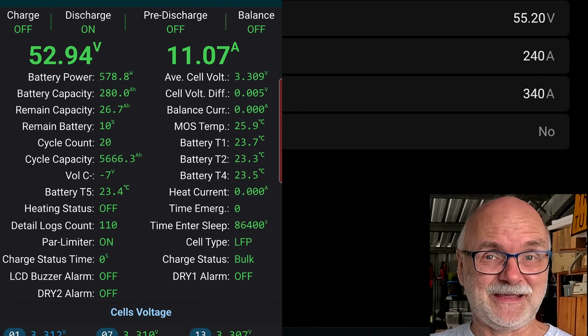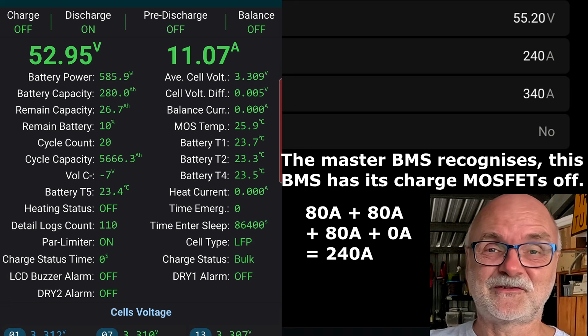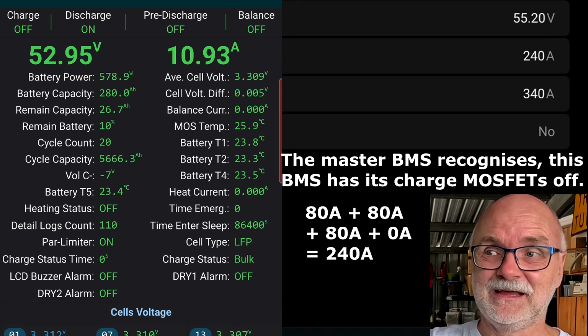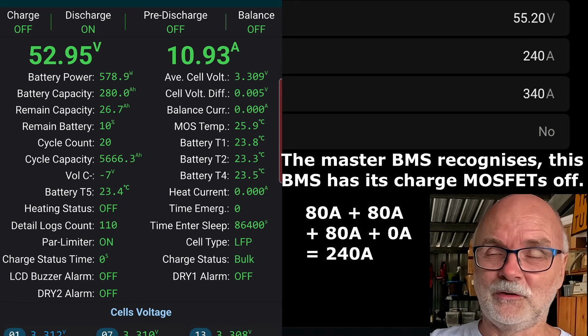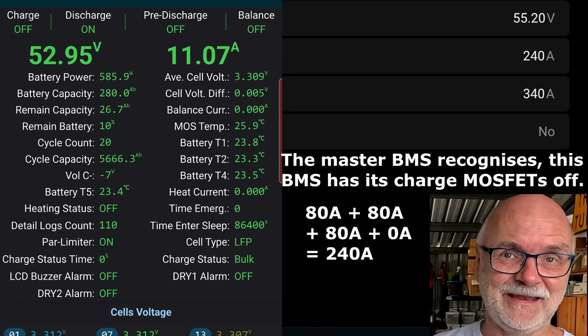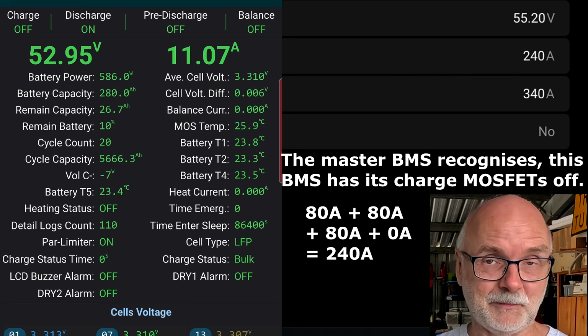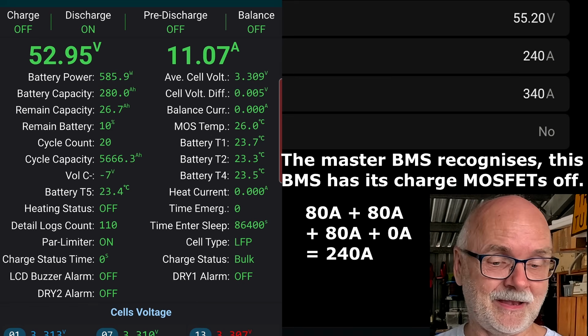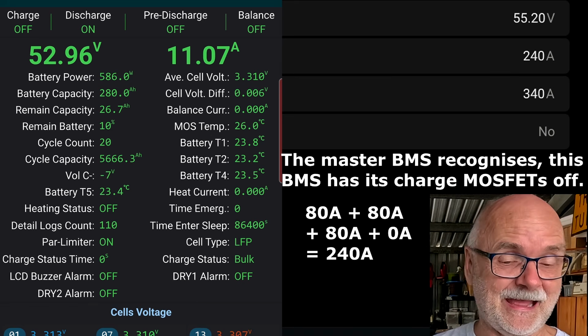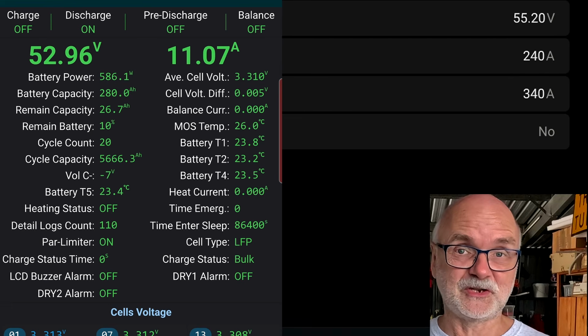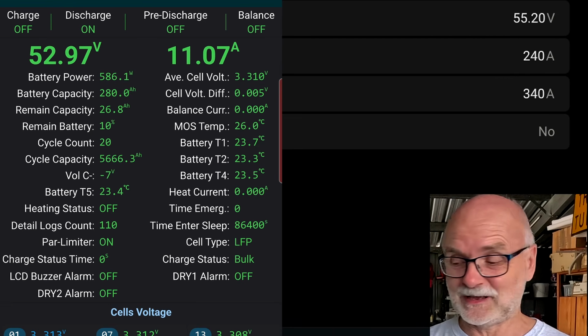Yeah, but this battery had a fault before and it is not part of your system anymore. Yeah, we are charging reduced. Only 3 batteries are getting their 80 amps, which we have set. But this battery here is not part of the game anymore. Even if it takes 11 amps, we will not see a full charge current limit again until we go under 5 amps. So let's see if this works actually. I think it was 5 amps.